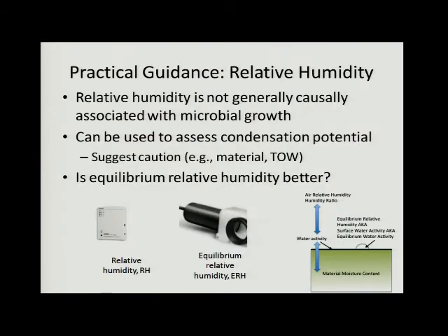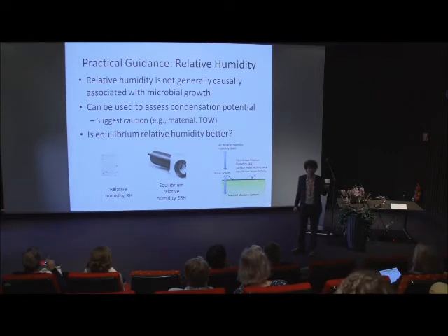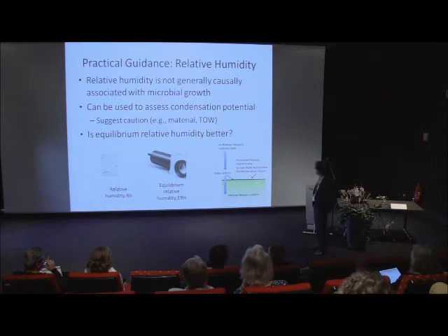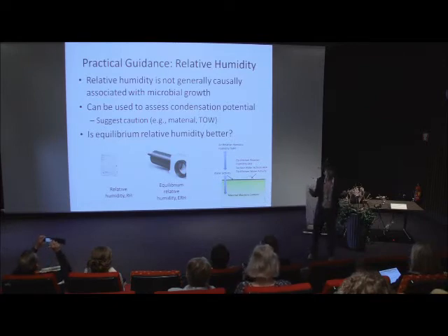So what a lot of people are doing is using relative humidity as a surrogate for water activity. And the comment I'd make about relative humidity is that, to my knowledge, no one has ever causally associated moisture in the air with any kind of microbial growth or proliferation. So microbes, as far as I know, are not pulling moisture molecules out of the air. At least I haven't seen any evidence of that anywhere. And so what a lot of people do, at least in a practical sense, is use relative humidity to look at condensation potential.